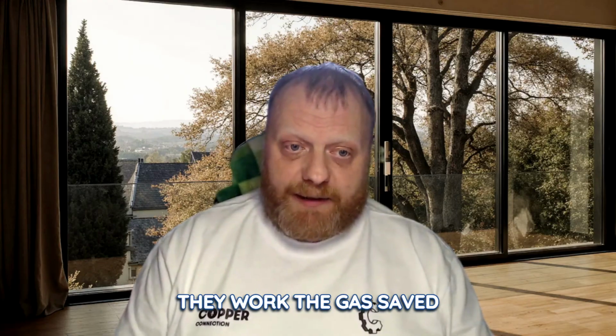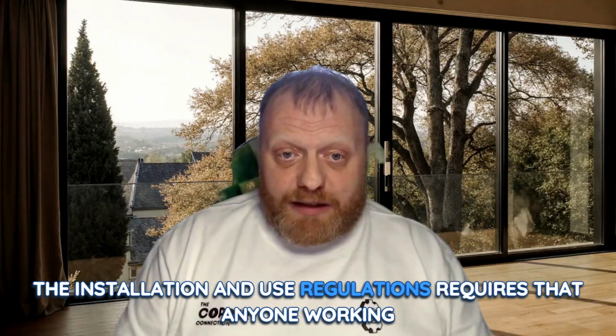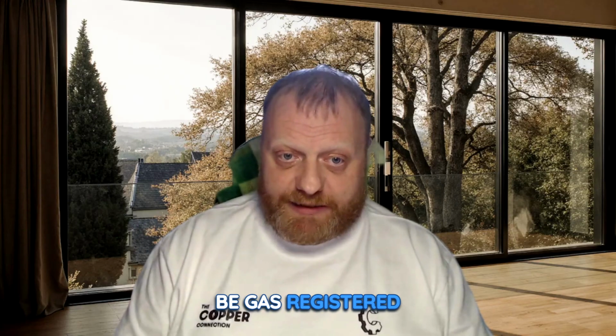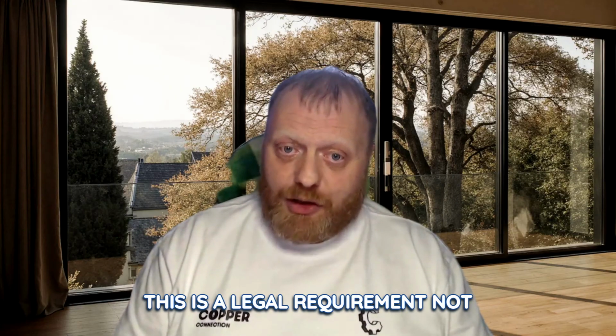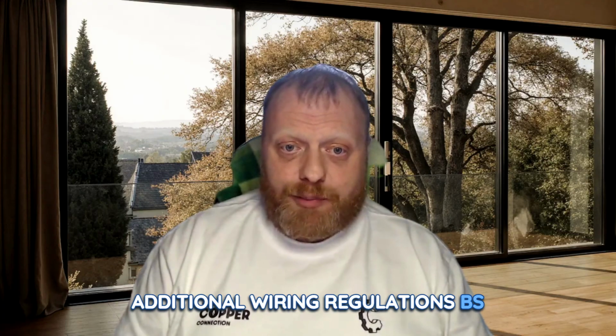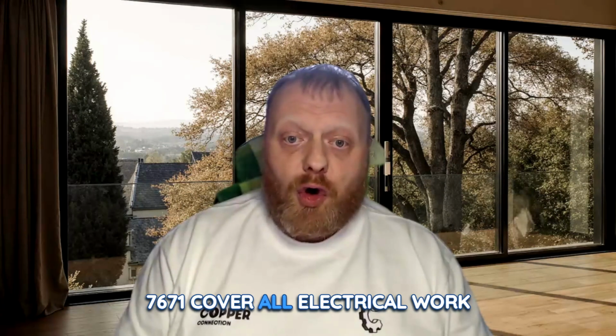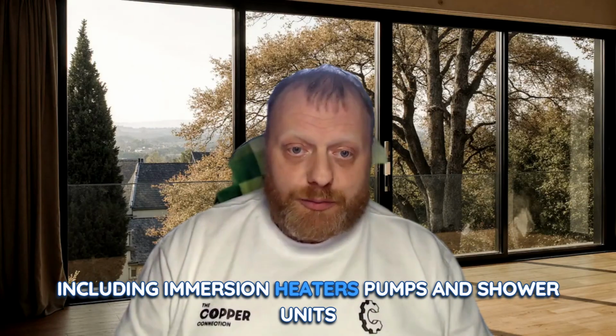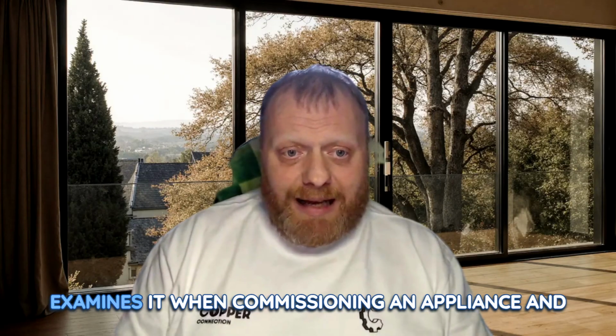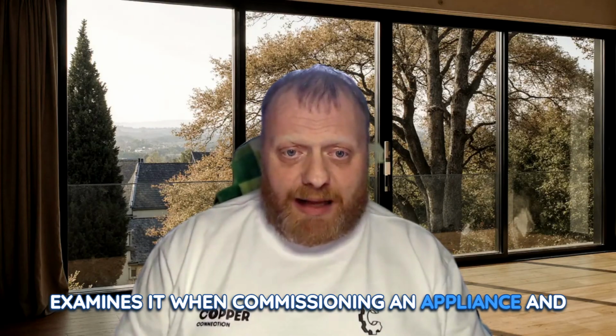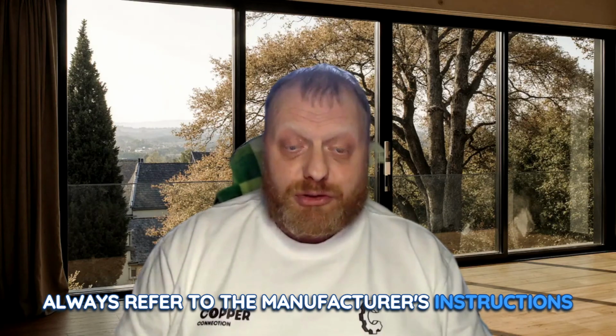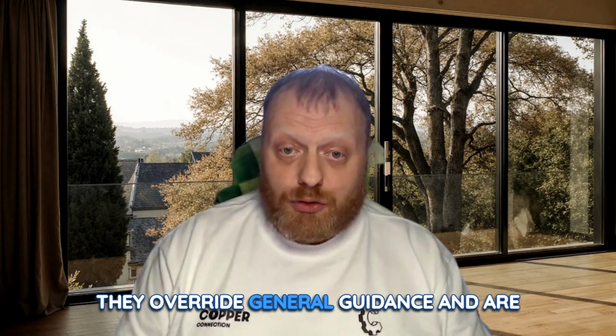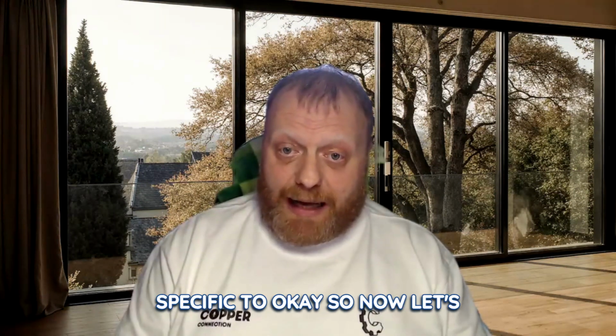They work together. The Gas Safety (Installation and Use) Regulations require that anyone working on gas appliances must be gas registered. This is a legal requirement, not optional. And the IET 18th edition wiring regulations, BS 7671, cover all electrical work, including immersion heaters, pumps, and shower units. Exam tip: when commissioning an appliance and checking flow rates and pressure, always refer to the manufacturer's instructions. They override general guidance and are specific to that appliance.